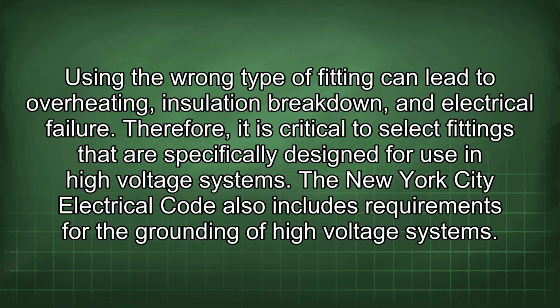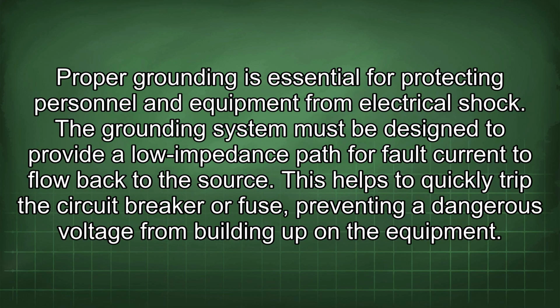The New York City Electrical Code also includes requirements for the grounding of high-voltage systems. Proper grounding is essential for protecting personnel and equipment from electrical shock. The grounding system must be designed to provide a low impedance path for fault current to flow back to the source.